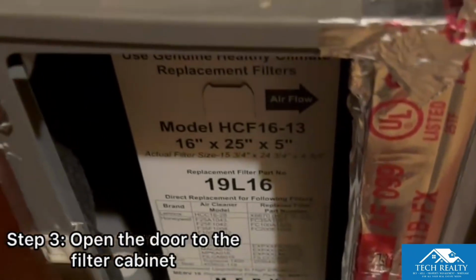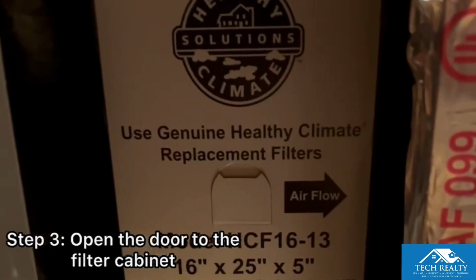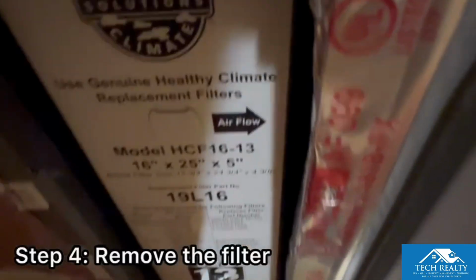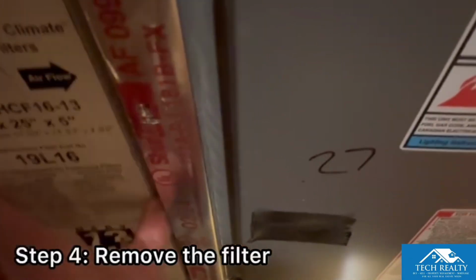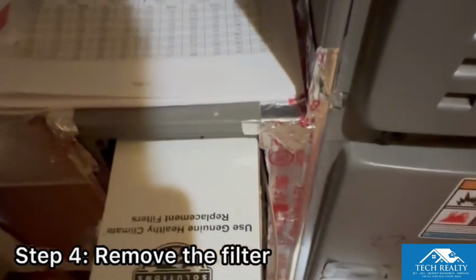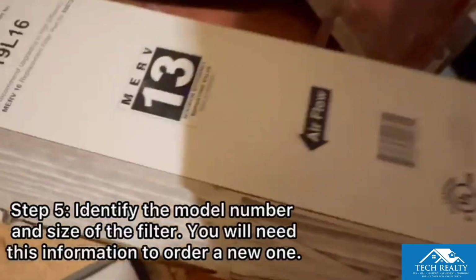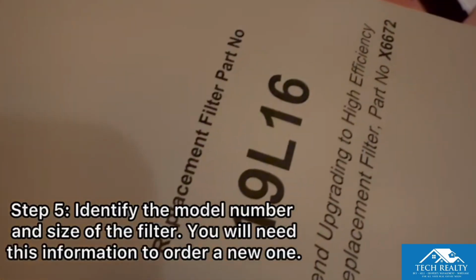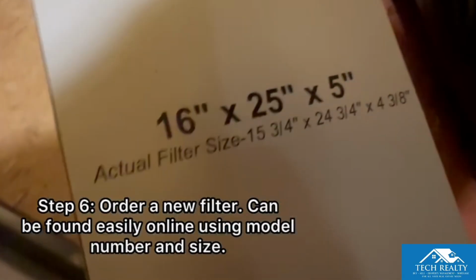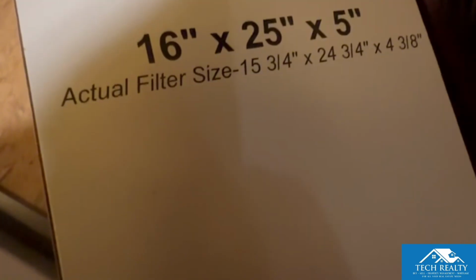Now, open the door to the filter cabinet. Here you can see all its information. Now remove the filter as you can see here. Here you can identify the model and the size for you to order a new one. Once you have it, install the new one and make sure the arrow of the filter matches the direction of the airflow.